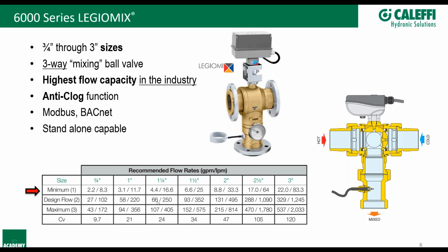Now, what happens if you don't meet minimum flow requirements on any mixing valve? It doesn't matter if it's ours or anybody else's. We all have minimum flow requirements. I will tell you that they don't blow up. They don't cause big catastrophic issues, but you're going to get unstable outlet temperatures. It could be too hot. It could be too cold. It could hunt and things like that.